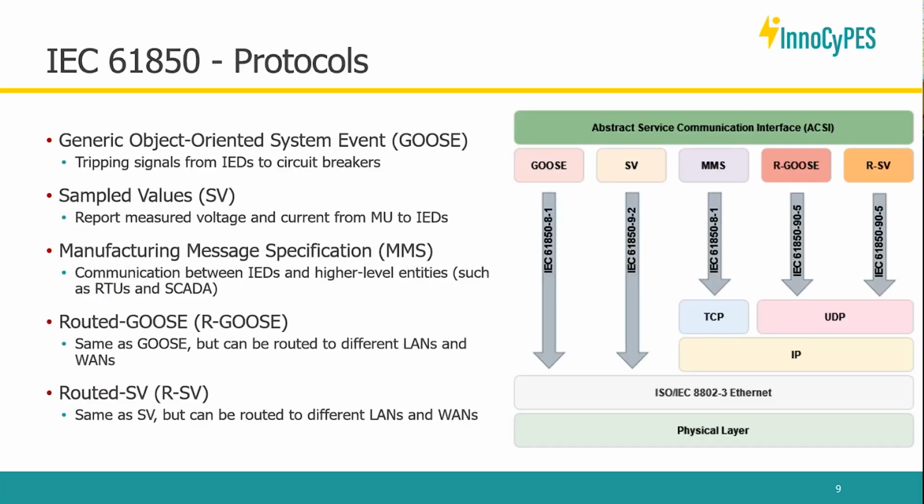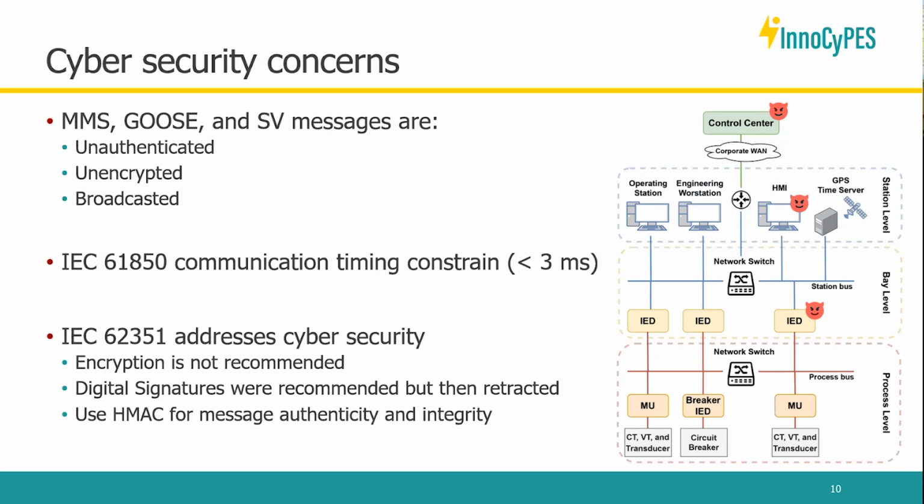There are simple ciphers which meet these real-time requirements. They are already available. They are not asymmetric, they are symmetric key-based. Yes, for instance, the standard suggests using HMAC, which is a symmetric key authentication system, not encryption. So it is recommended. The industry is testing it, but there are issues because legacy systems are not that easy to update to support message authentication codes.